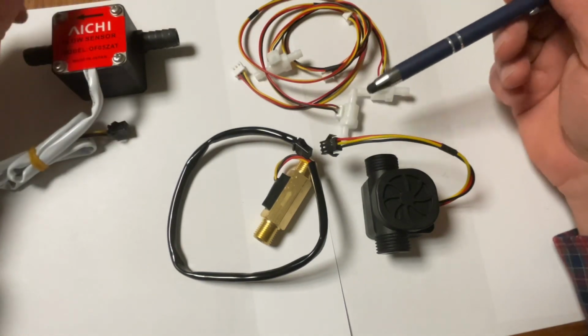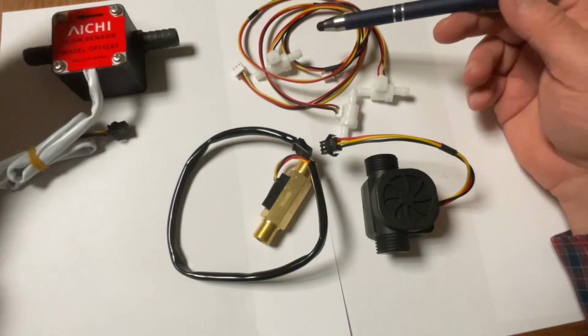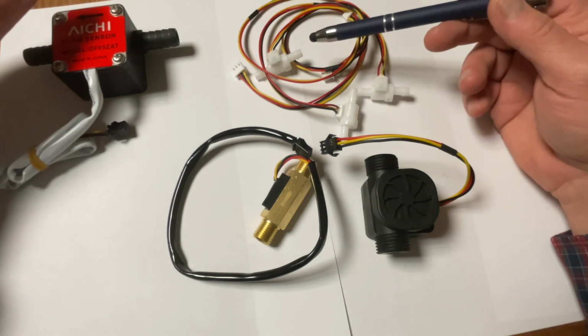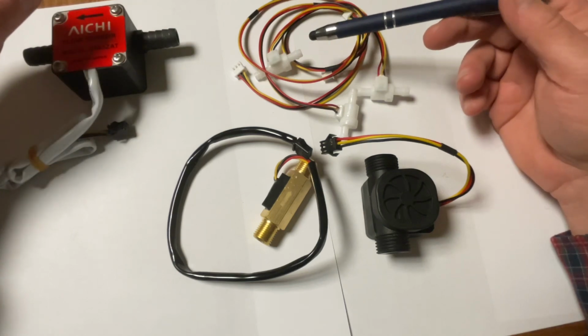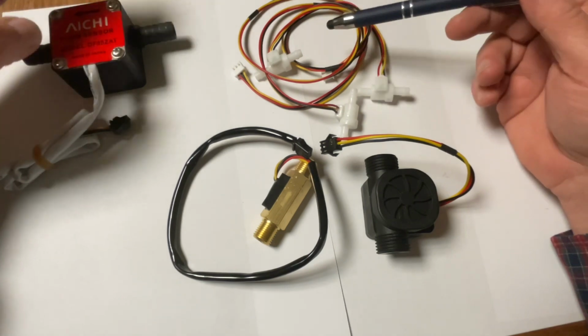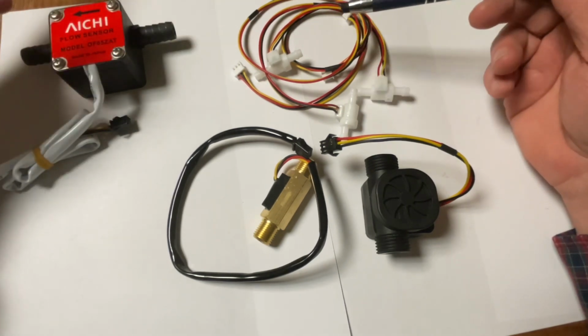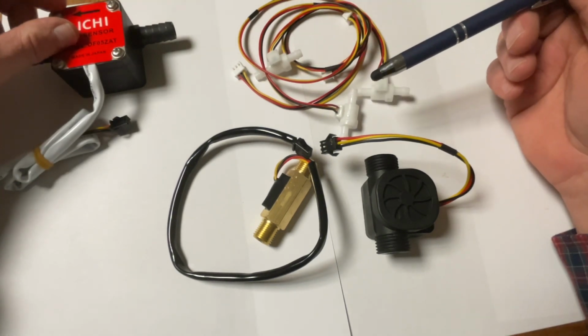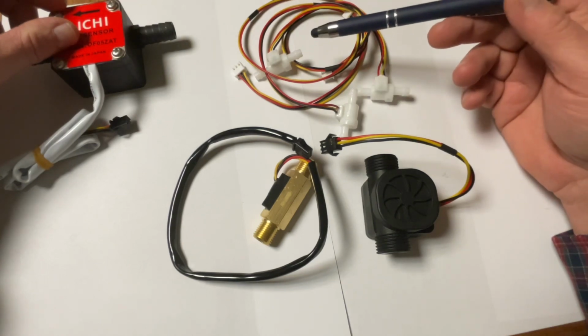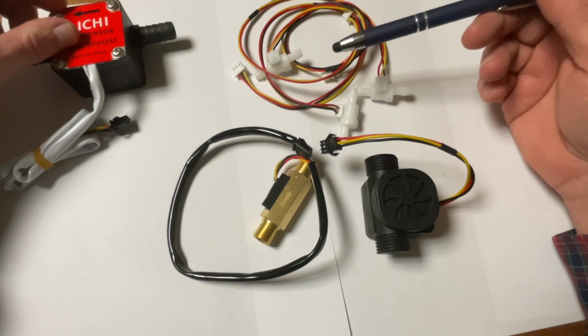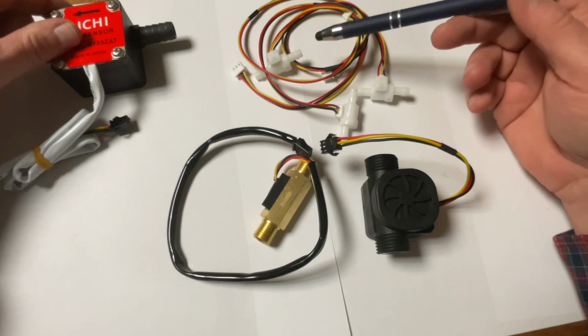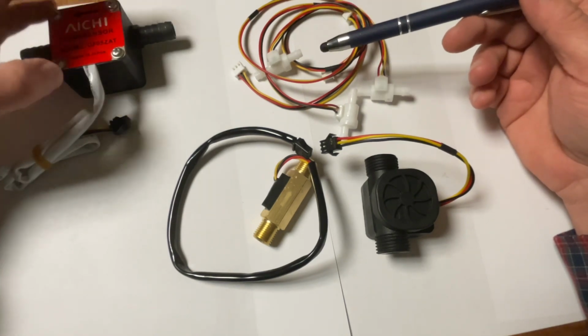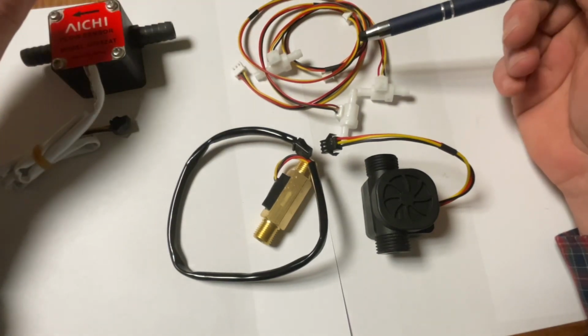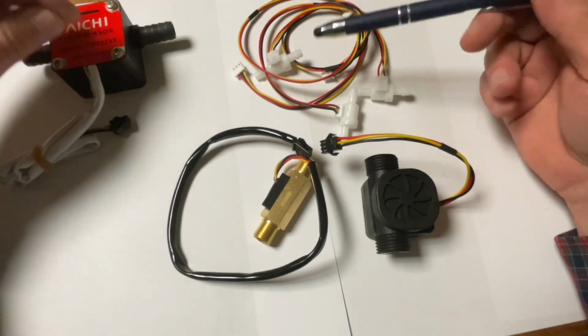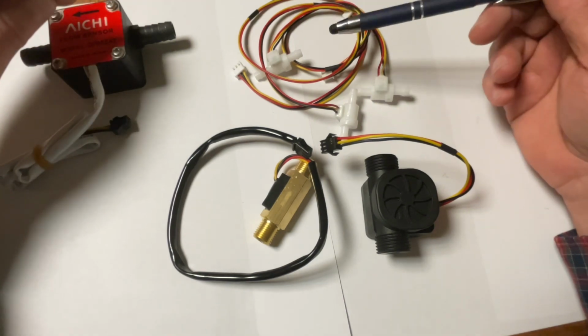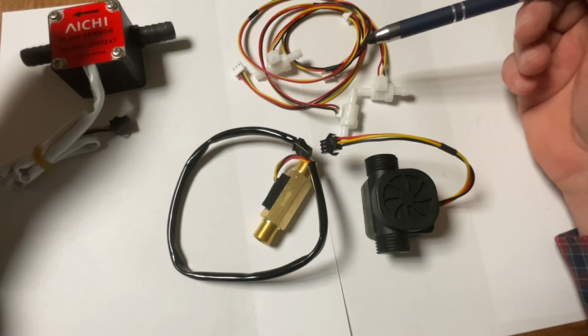So I will experiment with these to get a feel of the flow rate and how they're indicating this, and whether they really need a very high flow rate or would work with lower flow rates, and then see what kind of accuracy we get. The beauty of digital sensors is this, and that's why I did that project for Bosch back in, I think it was 87 or 88: we can change the sensitivity through the software I would write. And I can also do a whole bunch of other things by knowing the sensor. So the circuit board with the display on it is going to be universal, and we can interchange sensors and see which sensor will work better for our application, and we will get to the desired results at a lower cost.